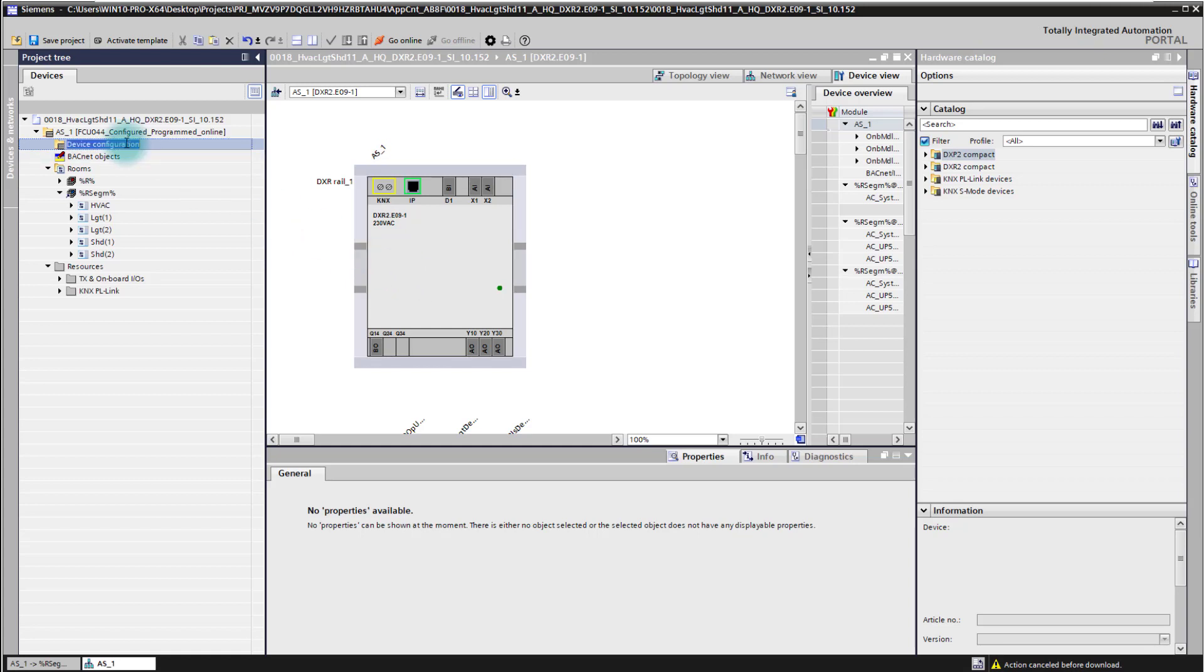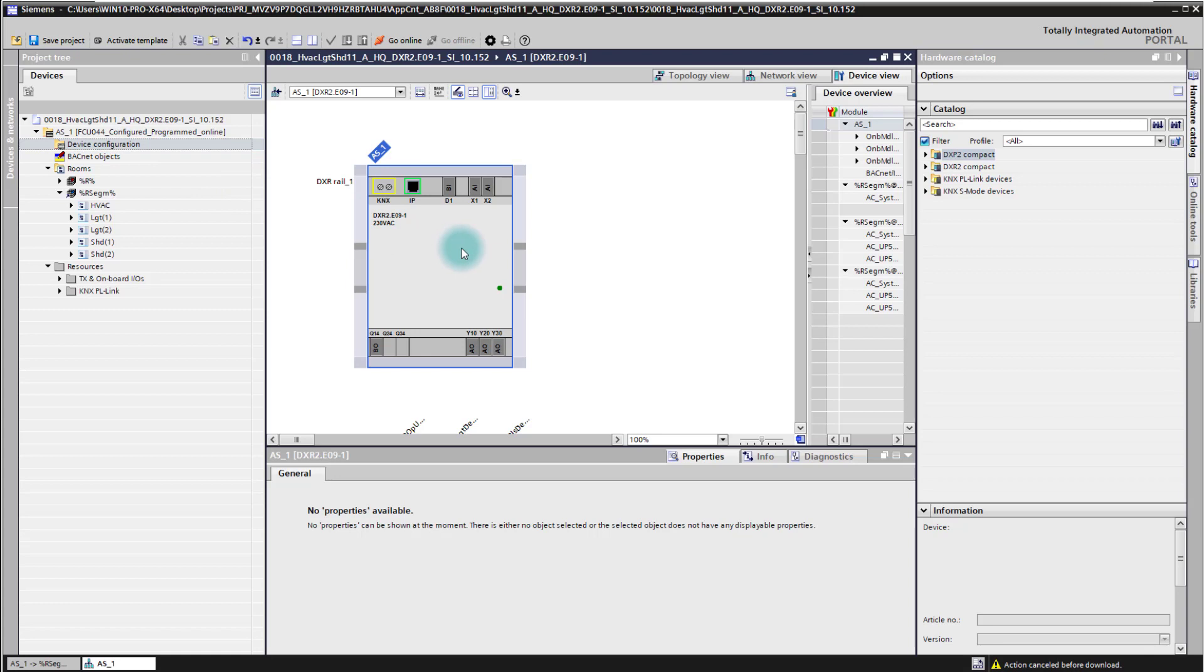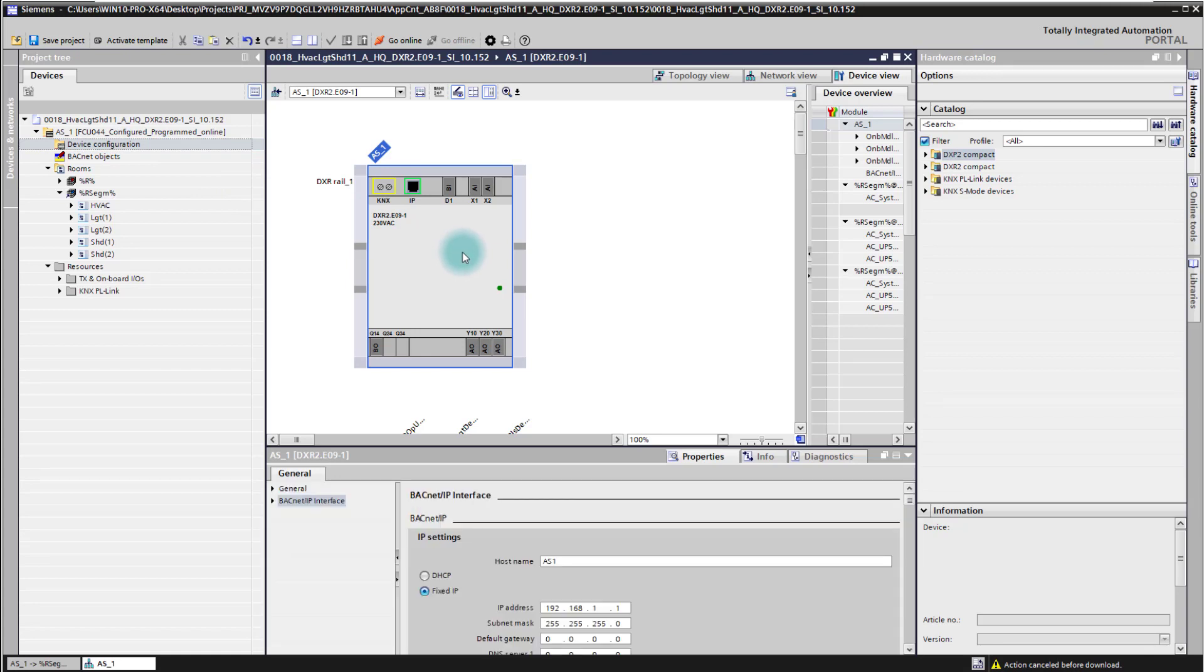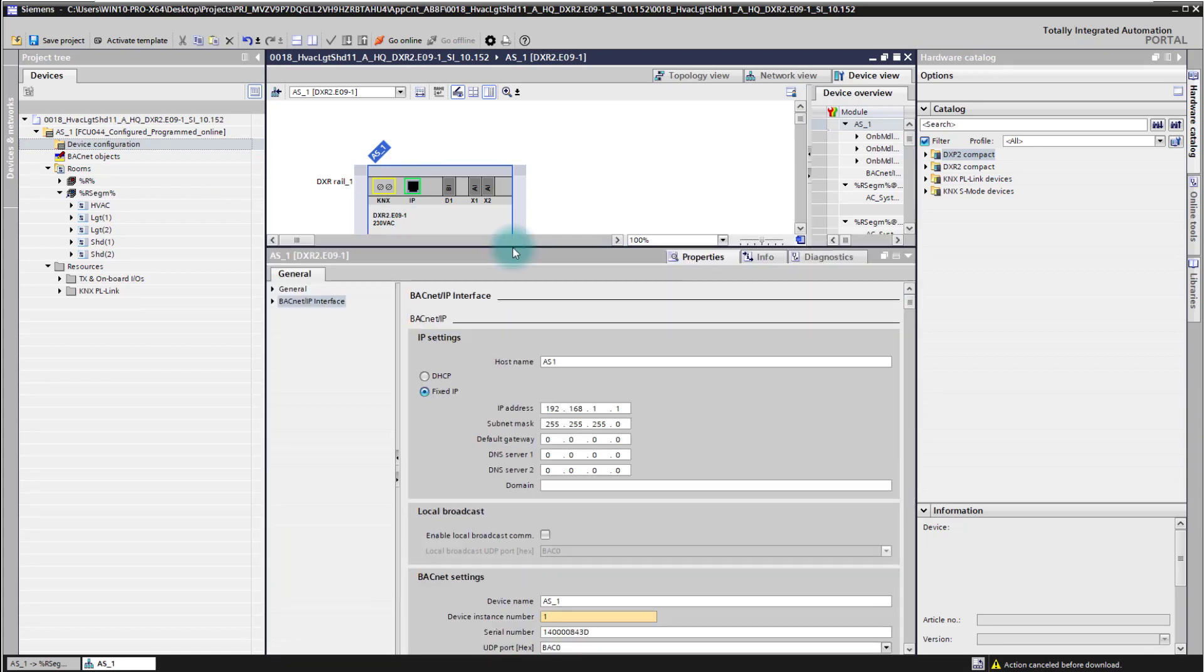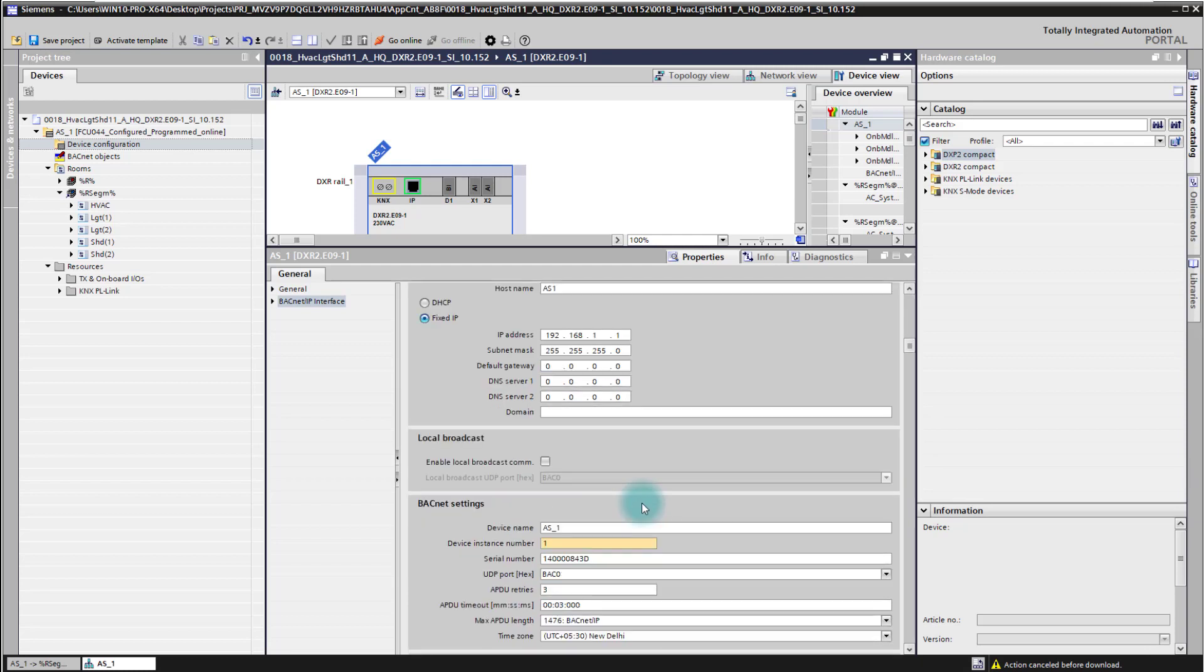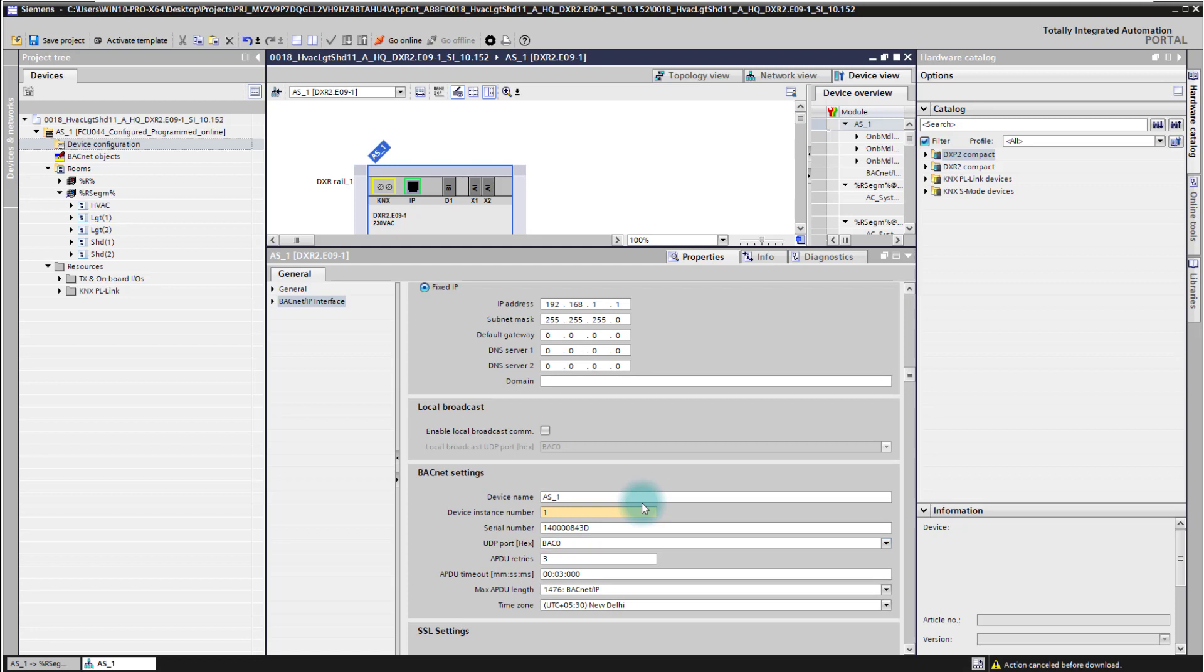If you go to device configuration you select the controller, you see in the property the BACnet interface settings. I have set here the BACnet settings and the IP address for my testing infrastructure, the controller I'm going to connect with. Please check also here the other BACnet settings like the UDP port and so on.